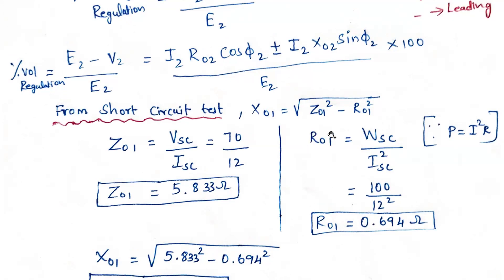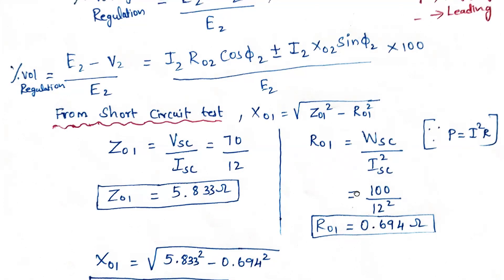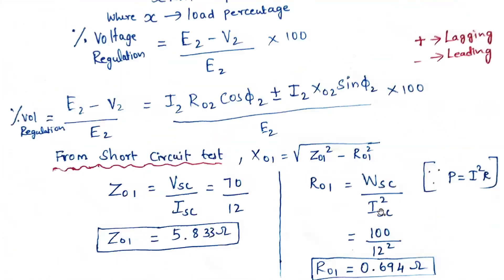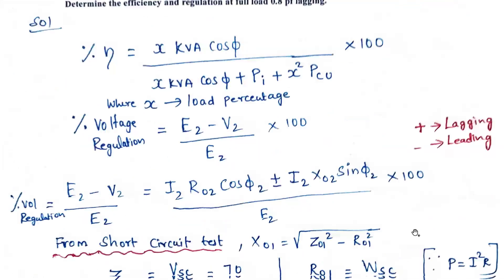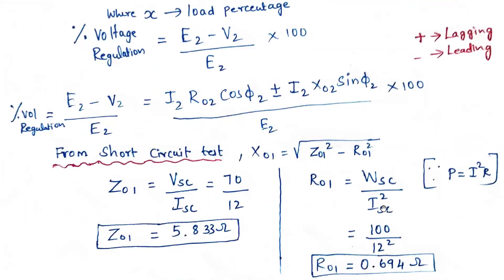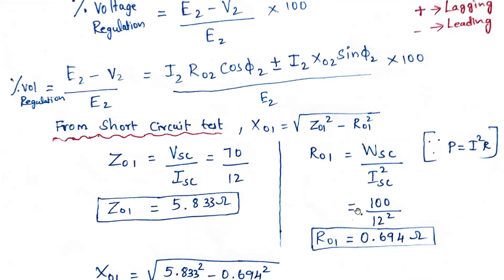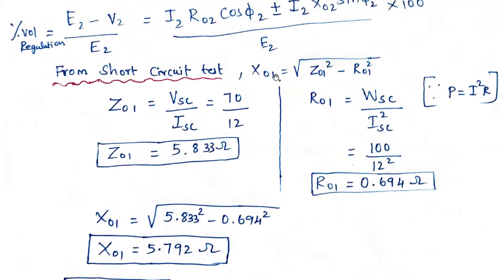Now we calculate R₀₁. Since power equals I²R, R equals P / I². So R₀₁ equals W_SC divided by I_SC squared. W_SC is 100 watts from the short circuit test, and I_SC is 12 amperes, so R₀₁ equals 100 / 144 = 0.694 ohms.